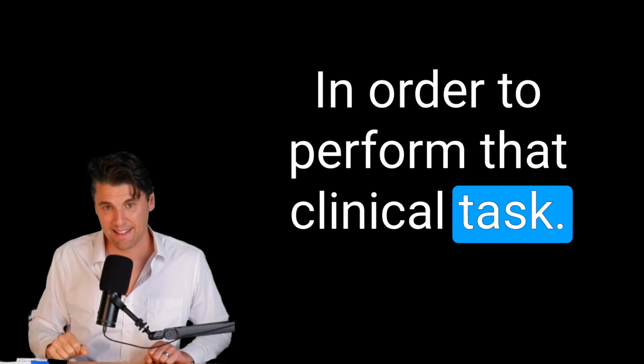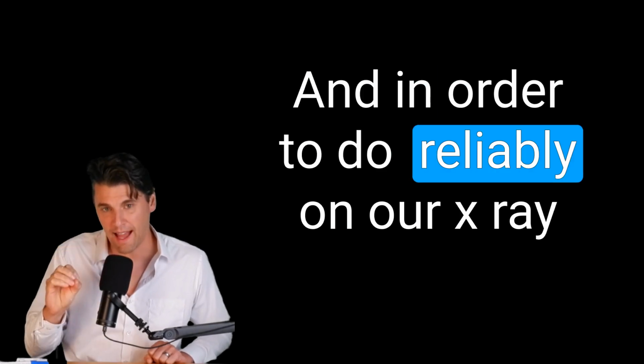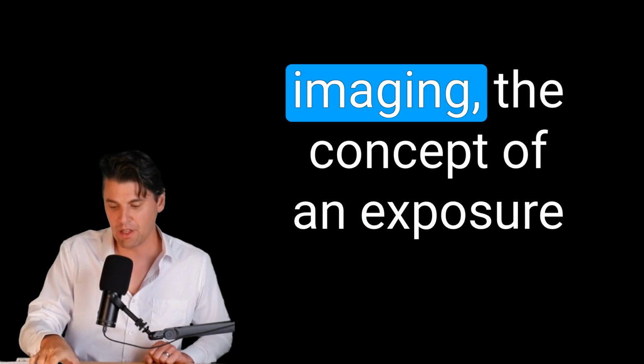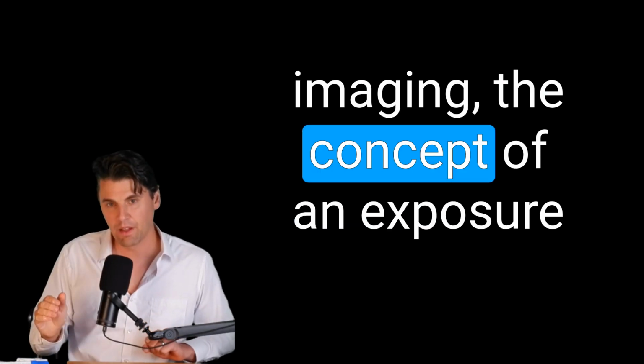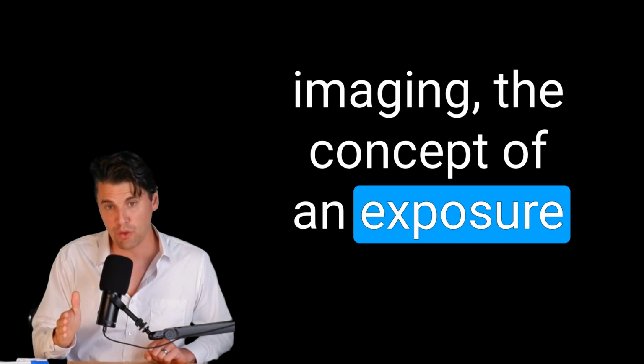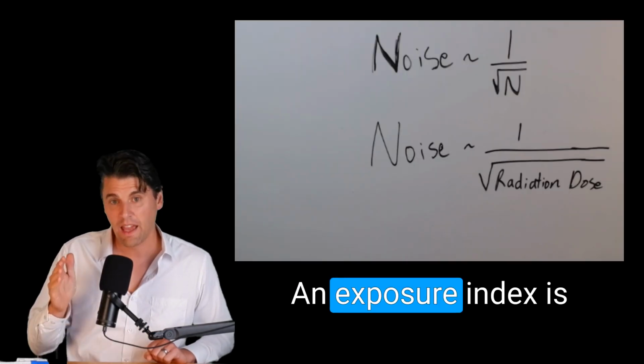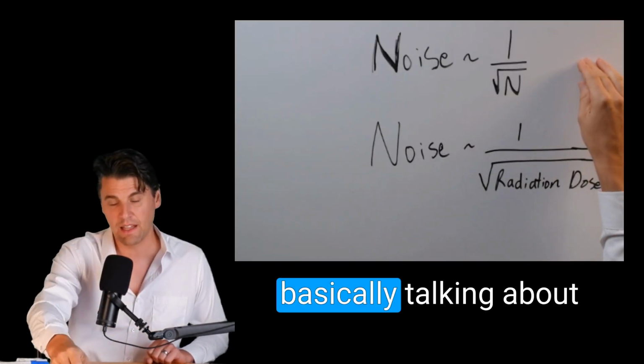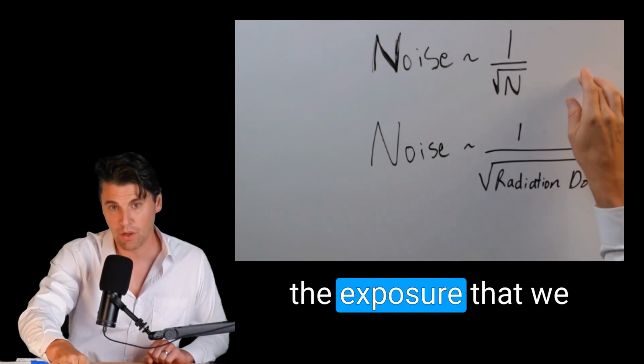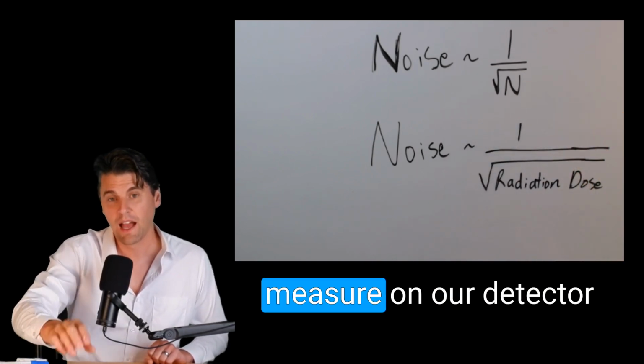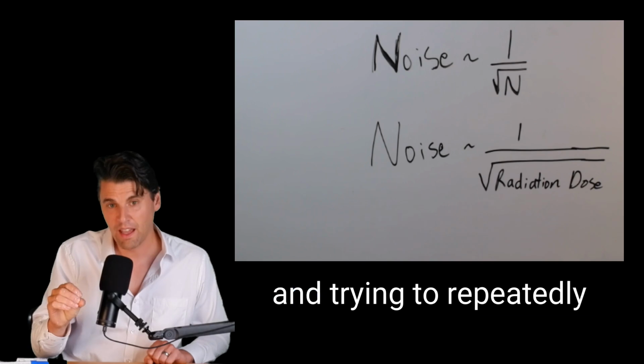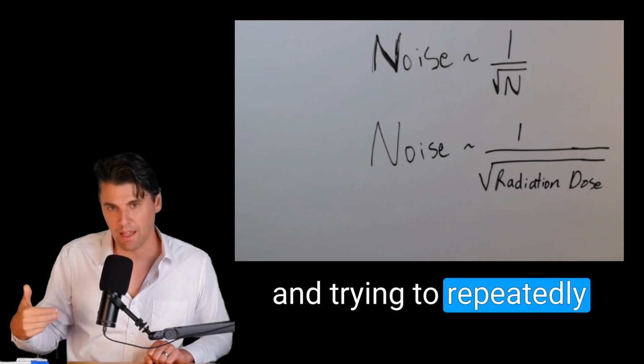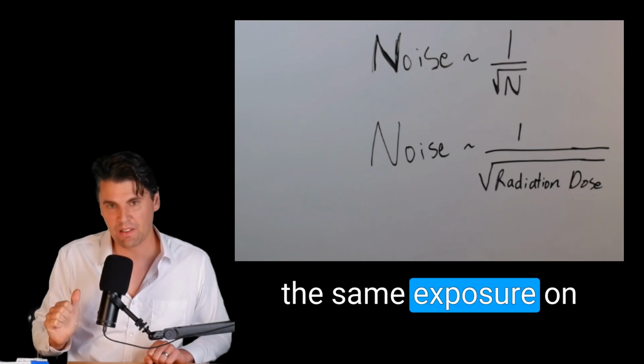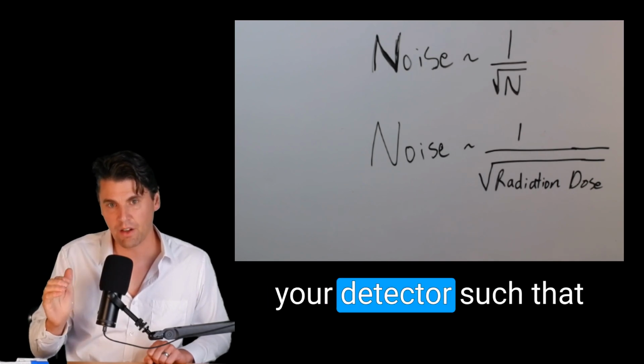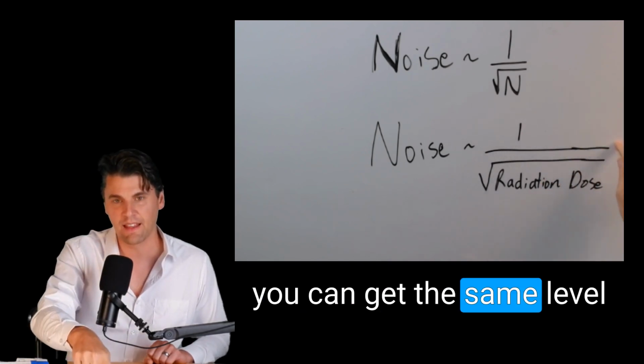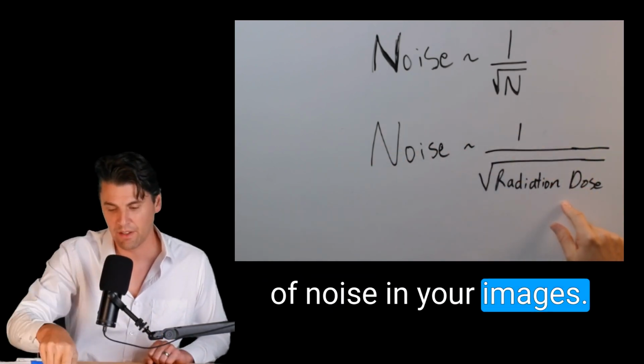And in order to do this reliably in our x-ray imaging, the concept of an exposure index has been introduced. An exposure index is basically talking about the exposure that we measure on our detector, and trying to repeatedly get the same exposure on your detector such that you can get the same level of noise in your images.